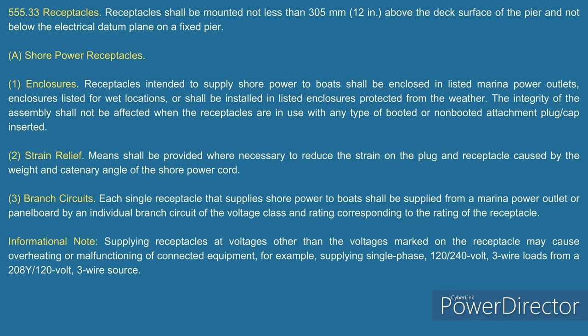Another interesting point, somebody said, well, if you go look at 422.16(B)(4) and pick that up, it says you can have an individual branch circuit. And I said, exactly, but you left out the most important part. What is that individual branch circuit feeding? It says a receptacle. And a receptacle is going to be put where? At an outlet, which is the box. And that's when your cord and plug are connected.